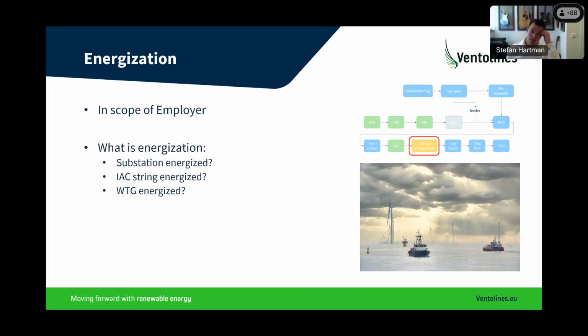First big question: what is energization? I've seen ambiguity, both in speech and in contracts, on the definition of both energization and grid available. Is that a substation energized? Is it the string of inter-array cables? Is it just a turbine? In my perfect world, the employer is responsible to energize the export cable and the substation. When a string is finished, the employer will switch the switchgear, the circuit breaker, on the substation and energize the string. However, the turbine energization should be the responsibility of the turbine contractor, because they installed the turbine, they commissioned it, and they have the full control.